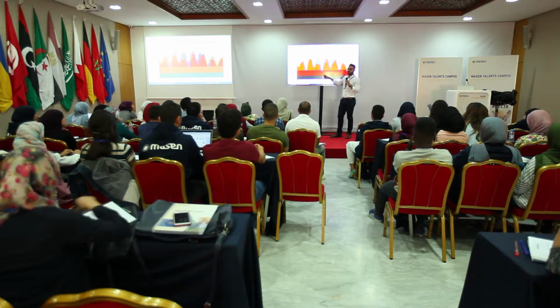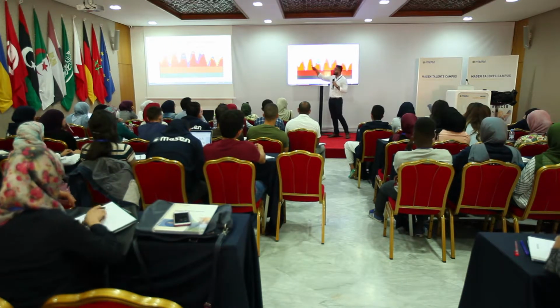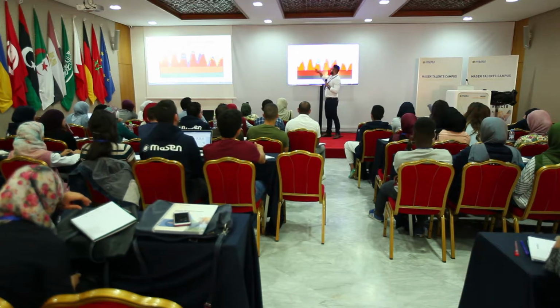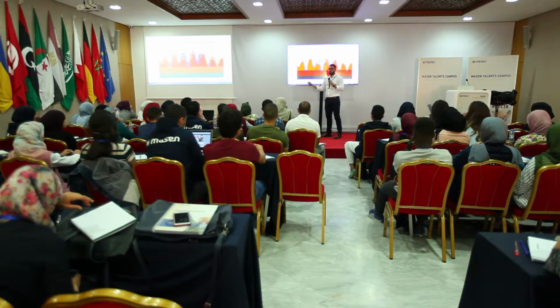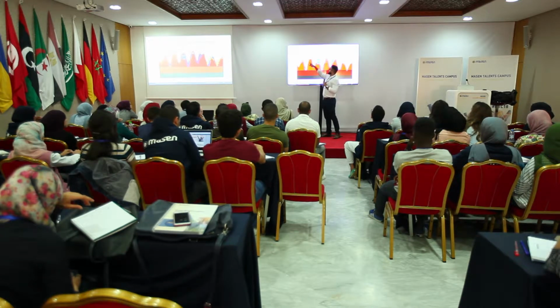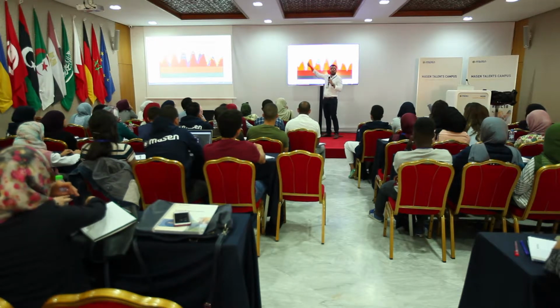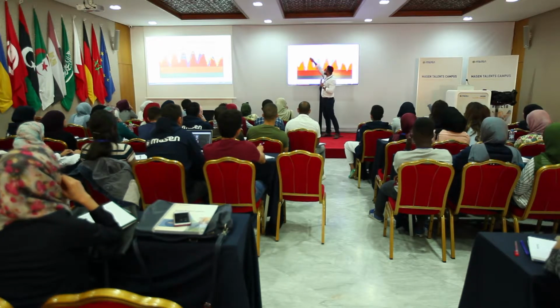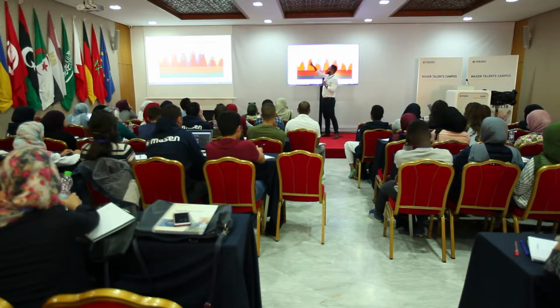So a 100 megawatt plant of PV produces 100 megawatt times 8,760, the hours in the year, times 30%, which is the usual capacity factor for a PV, compared to the CSP one, which would be 100 megawatt times 8,760 hours of the year, times a capacity factor that, depending on the storage, could go up to even 80 or 90%.